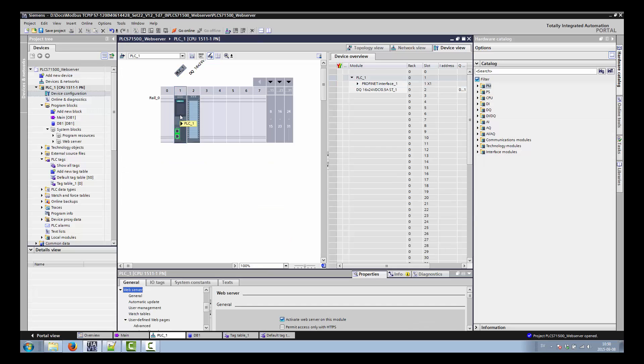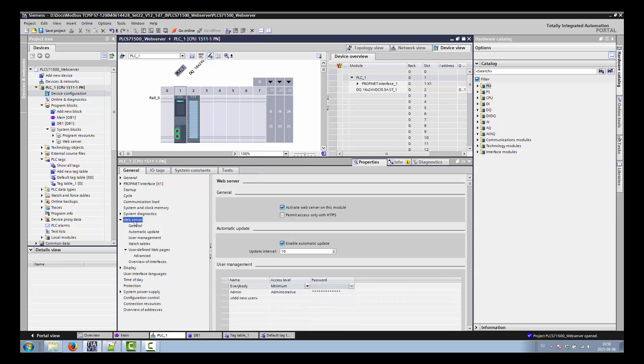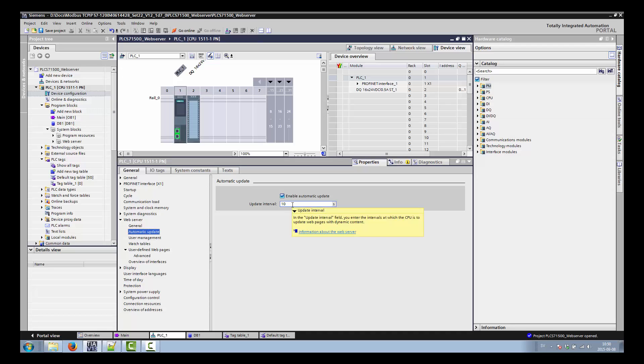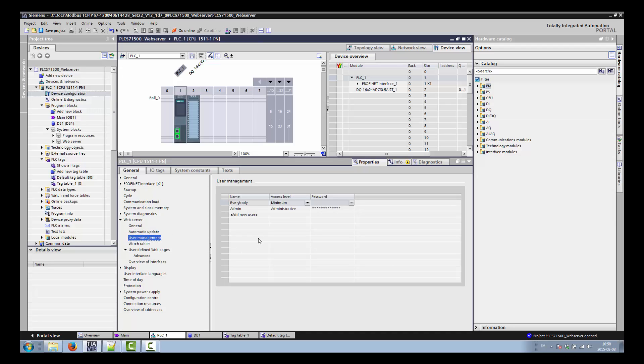Double-click on the CPU and go to Web Server > General. You activate the web server — this module should be activated. Then you have automatic update, which sets the update interval — how often you would like the page to be updated, in seconds. The browser will be updated once every 10 seconds. Under user management, it's very important to set a username and password to protect your CPU from outsiders. The username is case sensitive.